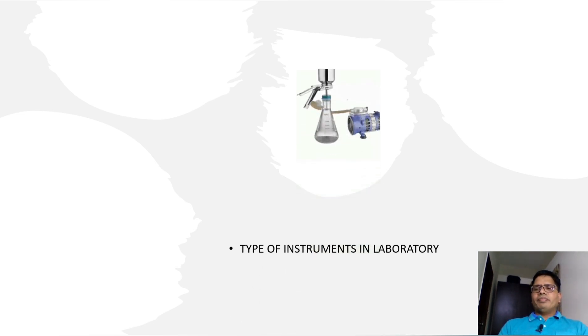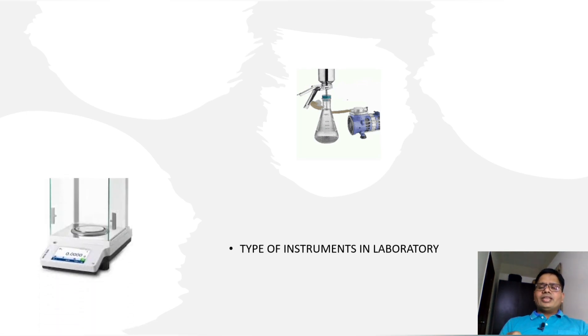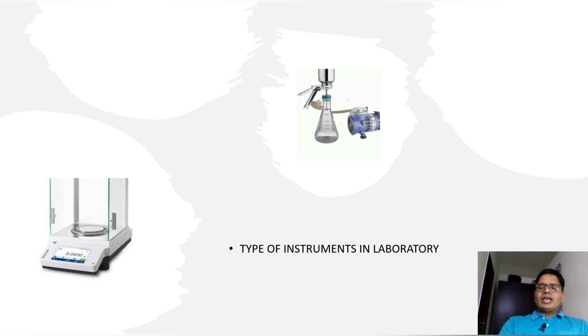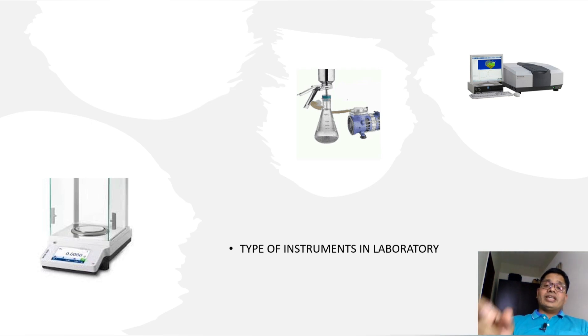Let's understand what types of instruments we use in the lab. First is the filtration assembly — this assembly doesn't generate any data and doesn't have control of physical parameters like temperature and humidity. Second is the balance — used for taking the weight of any material or liquid, but with no internal memory and not attached with software. When you take a weight, you just directly print to get the reading. Third is an instrument attached with one standalone computer system, controlled by a standalone PC.